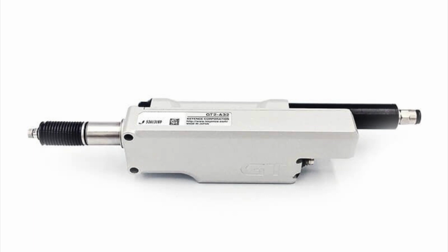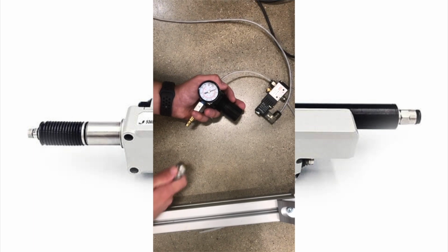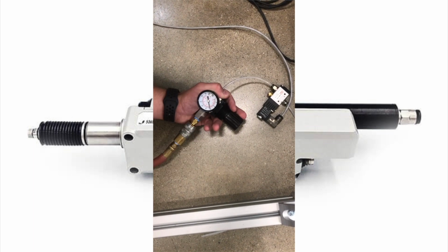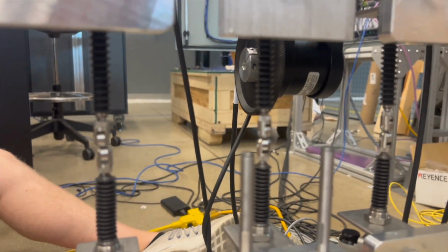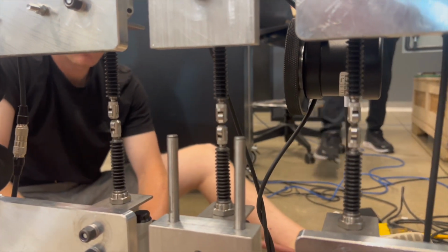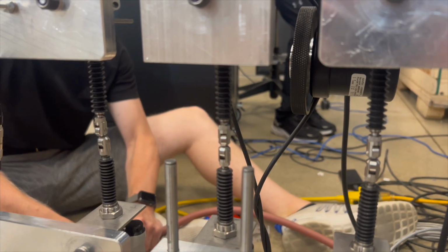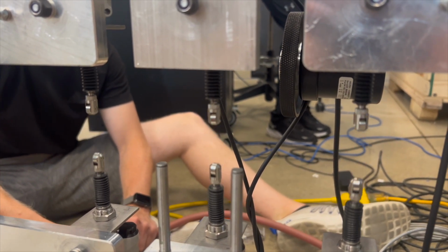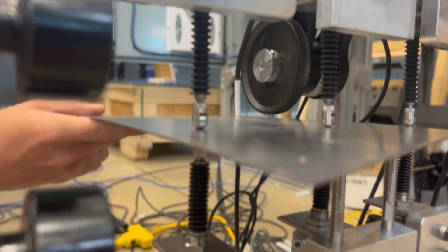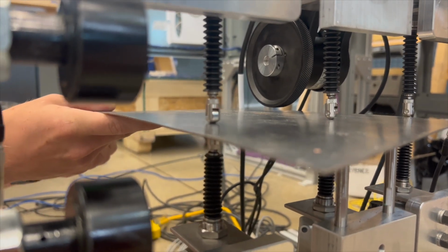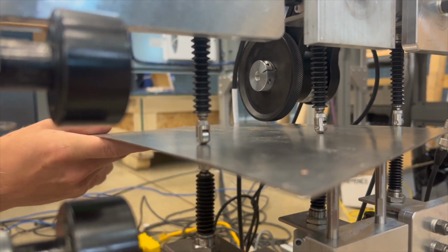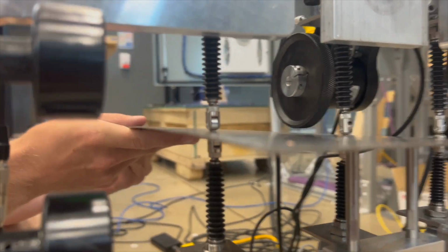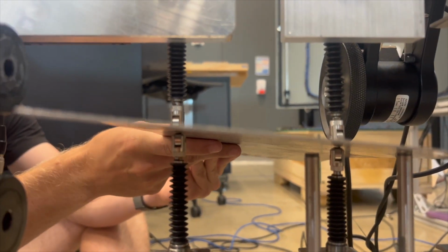The LVDT works by having a center core that is attached to the probe transfer a magnetic field from one set of internal windings to another, the amount transferred being based on the position of the core. In our application, the LVDTs are mounted with their contacts touching each other when fully extended. In this configuration, the LVDTs can be calibrated to a zero position and extended against the steel sheet. And when extended against the steel sheet, the sum of the LVDT measurements will be the actual thickness of the steel.